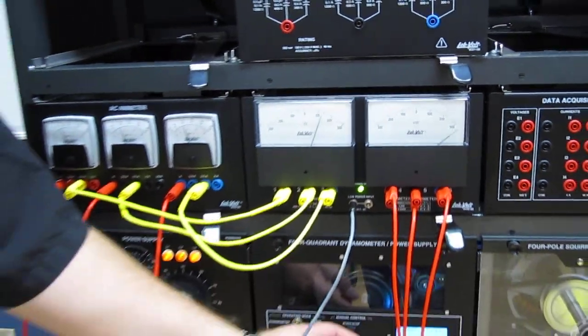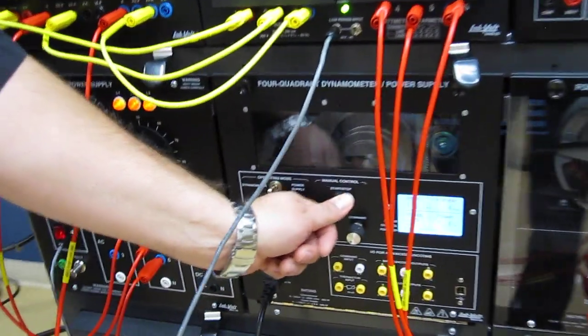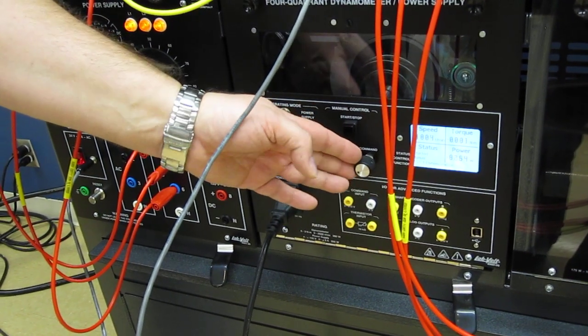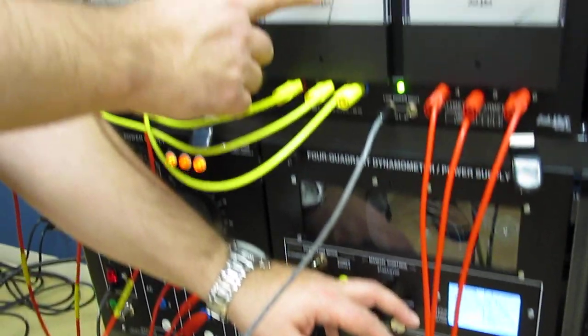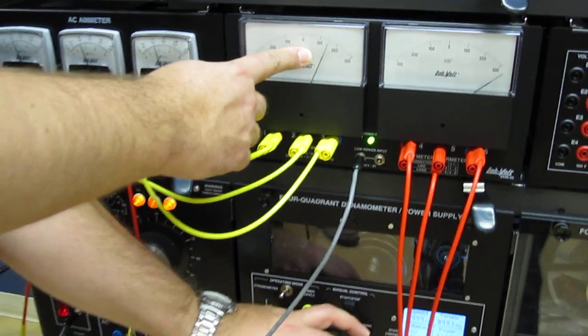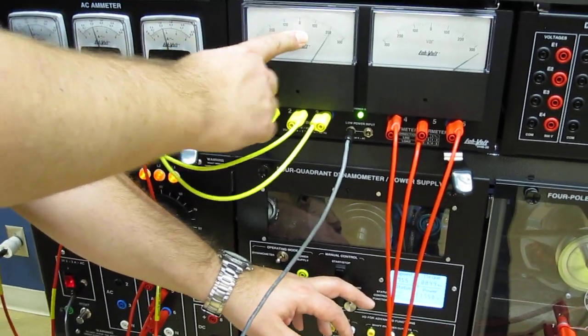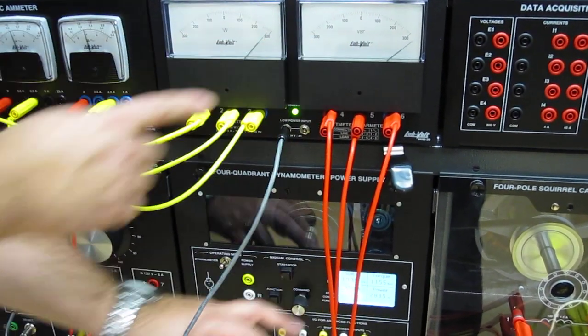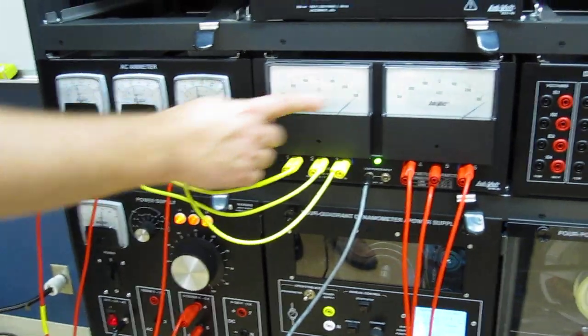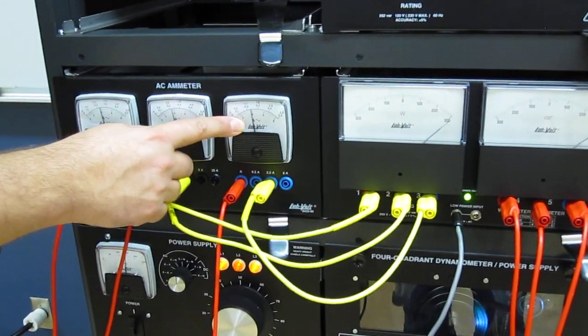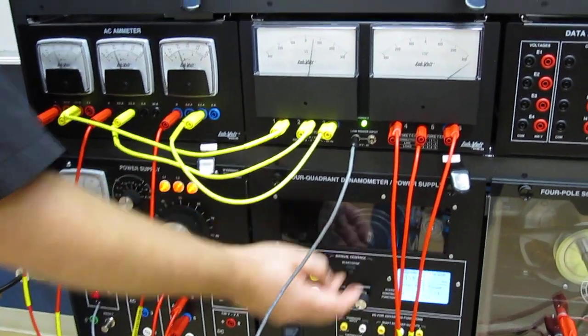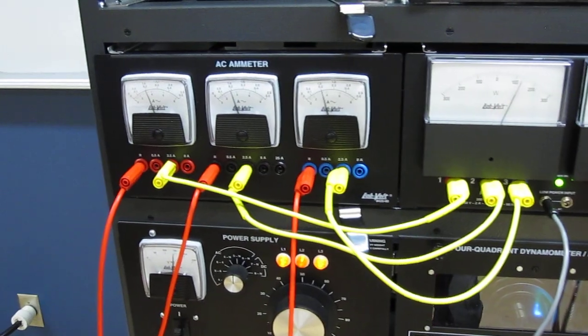When I go here and press the start button and increase the torque, I see that the active power is going up with the torque but the reactive power still stays at a very high rate. So more watts will give me more current. But even without the mechanical load I still have around 1 amp.